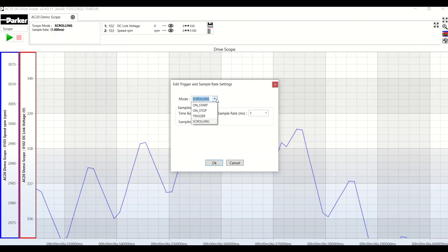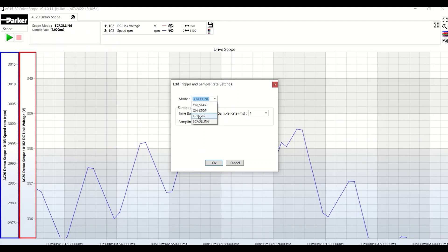Another selection we have on this screen is the trigger function. We have scrolling by default, which we have just seen. We have the onStart function, which starts the scope from the moment the drive is turned on, and the point at which this begins can also be delayed. OnStop is used to see what happens when dynamic braking occurs. In this case, we will choose to start the scope at this time, which will avoid creating files which are too big. This can also be practical when we want to trigger on a fault which results in a stop, allowing specific recording without excess time on the recording itself. The most common function is the trigger function, which I will demonstrate.